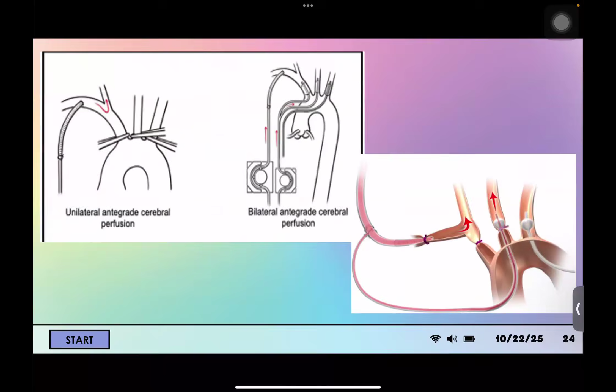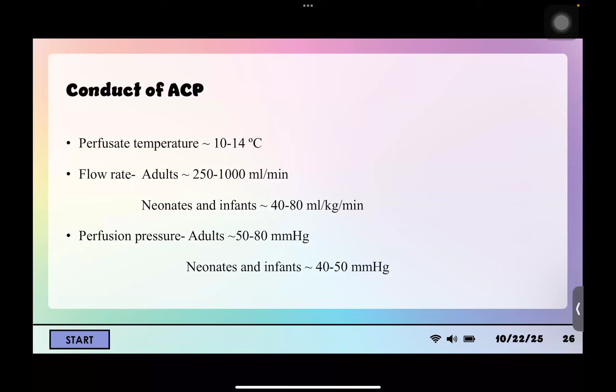Now coming to the conduct, the perfusate temperature should be 10 to 14 degrees Celsius. The flow rate for adults is 250 to 1000 ml per minute, and for neonates and infants, it's 40 to 80 ml per kg per minute. Perfusion pressure in adults should be around 50 to 80 millimeters of mercury, while in neonates, 40 to 50 millimeters of mercury. For unilateral antegrade cerebral perfusion, occlusion of the arch vessels will ensure perfusion of the circle of Willis.